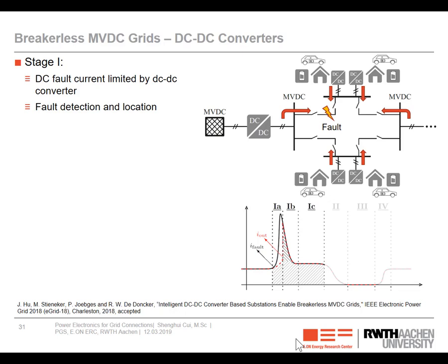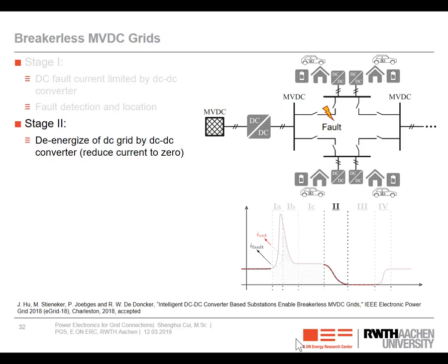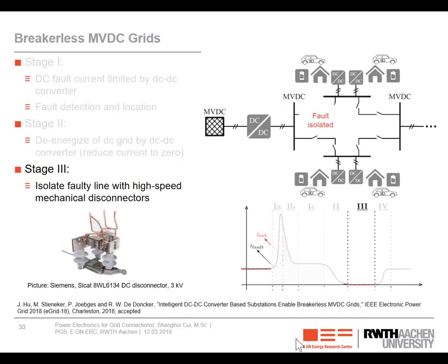But here we should keep in mind that we shouldn't extinguish the DC current immediately, because if there's no current flowing, then it's impossible to detect and localize where the fault happens, and it's impossible to isolate the fault. So here, the DC-DC converter will output a certain amount of controlled DC current continuously until the protection schemes detect where the fault is, and then it extinguishes the DC current afterwards, and then the fault can be cleared by mechanical disconnectors. Because when the disconnectors are opened, the current is already fully extinguished. So in this case, it's very easy to address.